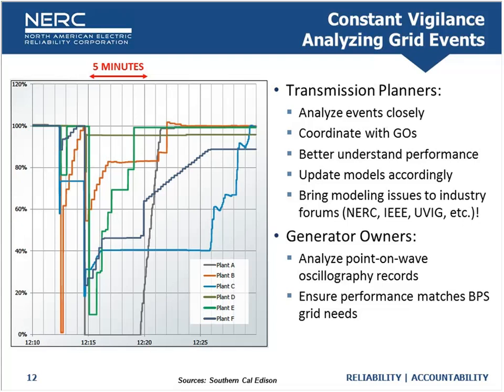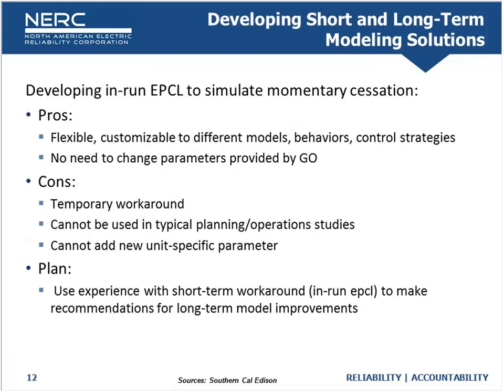We're trying to understand the underlying issues causing plants to trip, partially trip, use momentary cessation, or use partial momentary cessation — and why those are not being represented in the models. If you apply these same faults with the models we have today, you'll see a blip and a flat line and then a blip and a flat line. We wouldn't be capturing any of these types of things. So we have a gap and we need to figure out how to address it.